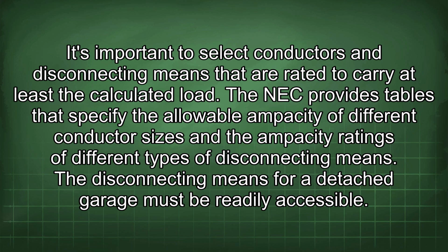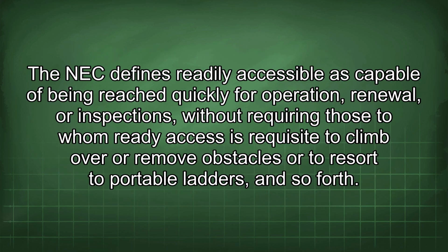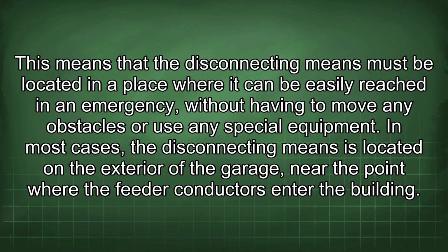The disconnecting means for a detached garage must be readily accessible. The NEC defines readily accessible as capable of being reached quickly for operation, renewal, or inspections, without requiring those to whom ready access is requisite to climb over or remove obstacles or to resort to portable ladders, and so forth. This means that the disconnecting means must be located in a place where it can be easily reached in an emergency without having to move any obstacles or use any special equipment. In most cases, the disconnecting means is located on the exterior of the garage, near the point where the feeder conductors enter the building.